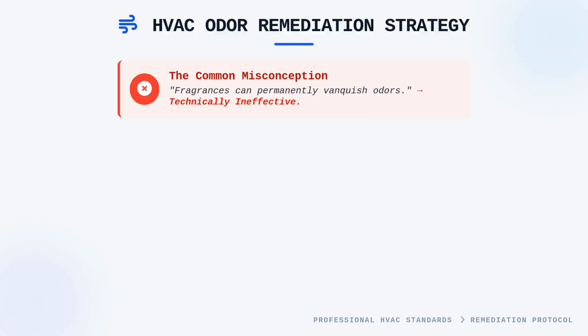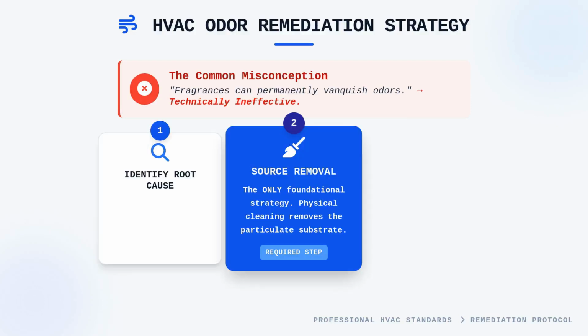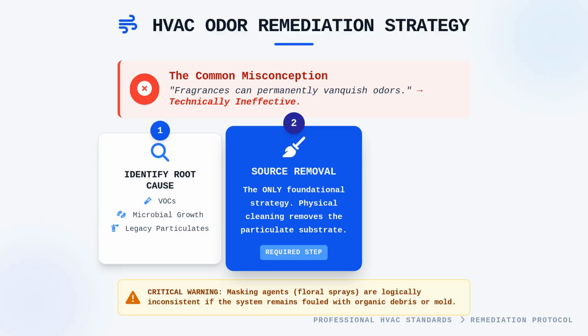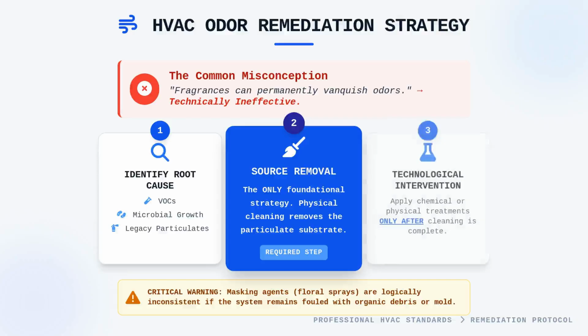Before applying any chemical or physical treatment, the technician must identify the root cause, which typically stems from volatile organic compounds, microbial growth, or legacy contaminants like fire-related particulates. You cannot simply mask the scent of cat urine or decomposition with a floral spray because the underlying organic matter will eventually reoffend the indoor air quality. If the system remains fouled with debris or mold, any deodorizing attempt is logically inconsistent and technically ineffective. A successful remediation plan starts with a physical cleaning to remove as much of the particulate substrate as possible before considering technological interventions.